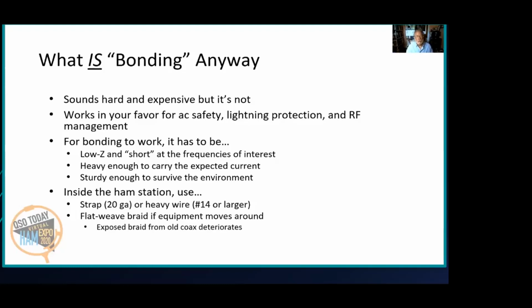That's why you see the requirements for number 6, number 8, number 4, number 2, heavy wire. It also has to be sturdy enough to survive the environment, particularly outdoors where it's often buried, and so it's subjected to frost heaving in the northern areas. We drive over it, we dig it up, hit it with shovels because we forgot where it was, and so it has to be sturdy so that it maintains its electrical connection under all sorts of mechanical abuse. Inside your station, though, the commercial and military standard is solid strap. 20 gauge strap. It can be something as simple as strips of flashing. It can also be heavy wire, all that Romex we saved because we can't bear to throw any pieces away. All that number 14 and number 12 wire is perfect for bonding inside your station. If your equipment moves around, you can use the tinned flat weave braid, the silver stuff.